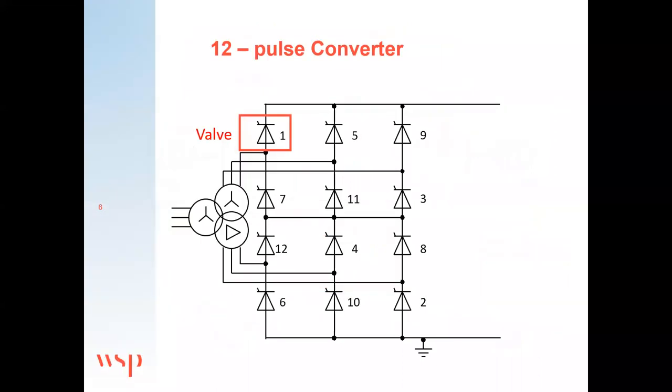If we look in more detail at the power electronic converter, we normally build what we call 12 pulse converters. So you'll see there are 12 individual thyristor switches. Of course, these are very high voltage systems. So each individual valve, as I've called it, is not a single thyristor. It is many, many thyristors connected in series, all switching coherently. But if we get our switching sequences correct and couple through a slightly more complicated transformer than I indicated before, we can create a DC voltage from the applied AC voltage by switching from red phase to yellow phase to blue phase.